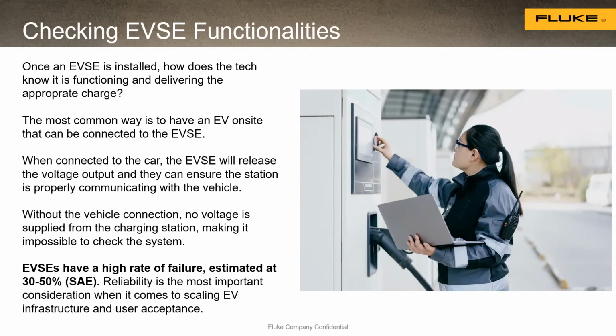It is, but you're right — when we start connecting and doing a lot of these grid installations, voltage, dirty voltage, harmonics, transients, all of that plays into effect of these types of installations. Could there be harmonic problems coming back from the system? You bet, and that's where we'd have to get some type of power quality analyzer and look back on that aspect. I haven't seen too many DC harmonic problems — I'm still learning, this is evolving, and I'm definitely not the most expert on this. From what we've learned, it's usually tied back into the AC side causing the problem. So you'd need a power quality unit, analyze the system, do a month-long record, and make sure vehicles are being plugged in and charging.